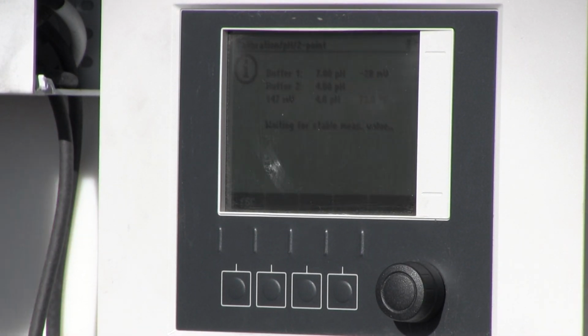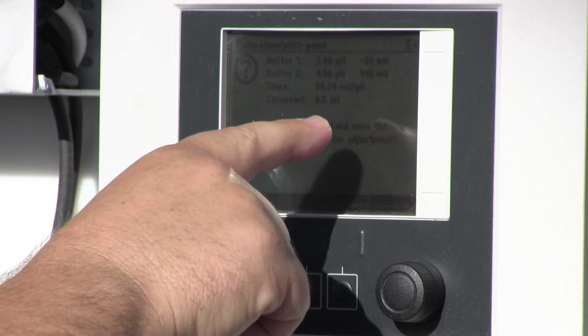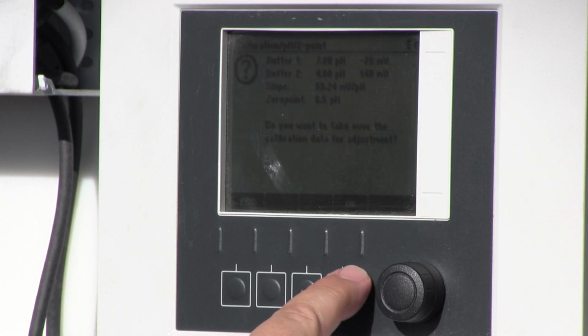It says waiting for stabilized measured value. It says, do you want it? It now gives me a little bit of information here. The buffer 1, buffer 2, the new slope and 0 point, and it says, do you want to take over the calibration data for adjustment? I hit OK. It says calibration is finished. Please clean the sensor before immersing.